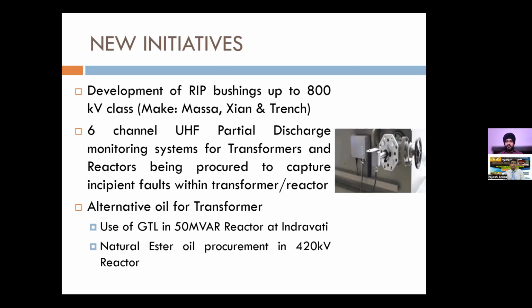And then UHF based PD monitoring system we have also purchased. We have purchased 4 sets. So these are used for online monitoring, and these are UHF based, and we are also going for acoustic based PD monitoring from third party vendors. So acoustic based PD monitors we have not directly purchased. We have purchased only UHF 4 sets that are being used. So these are used wherever there is a transformer or reactor where we suspect that there is some strong PDs inside.